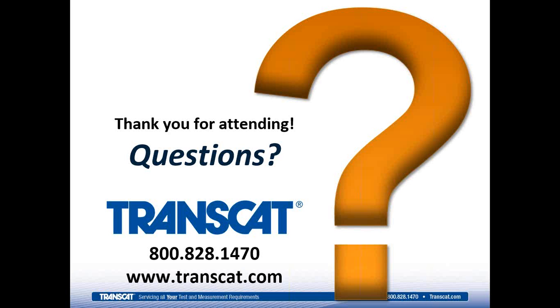Okay, thank you. Looks like we had a question back during your PAR calculations. Is this the same as the 4-to-1 accuracy ratio required by Z540? So I assume that's Z540.3 and talking about less than 2% consumer risk. That's really the concept that we're after: making sure that all of the components are taken into consideration when you're making a measurement, including the instrument accuracy, the uncertainty of the calibration of that instrument, the resolution of the instrument, and any operator error or variations that come from the operators using the instrument for the process. All of those things taken into account give you a process uncertainty ratio, not just a process accuracy ratio. And it takes all of that into consideration to help reduce the risk in making a decision about a product that is good when it's really bad, or that it's bad when it's really good.